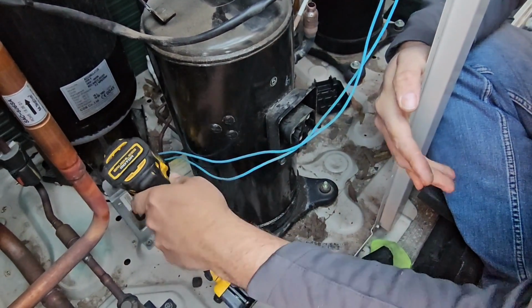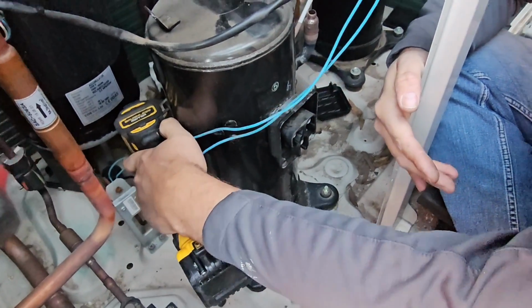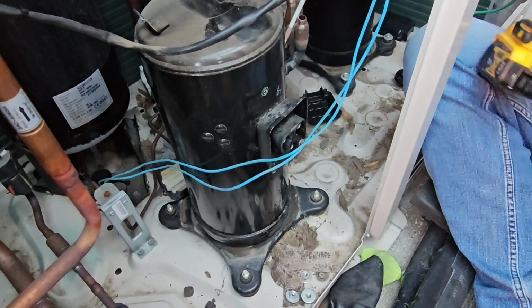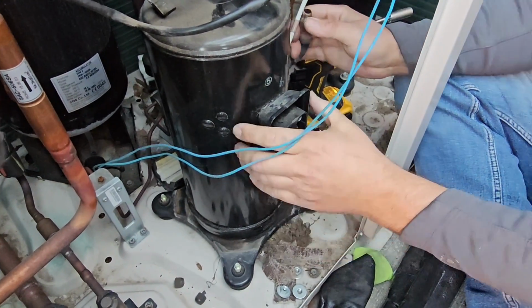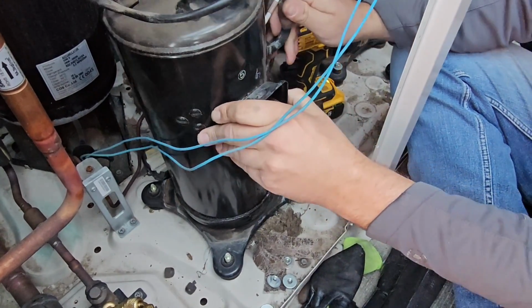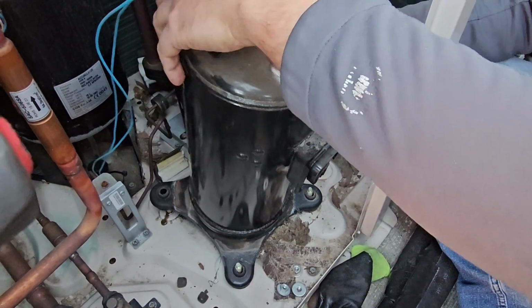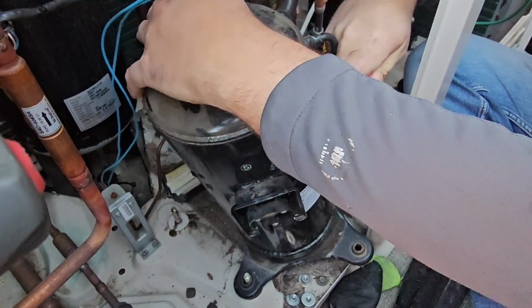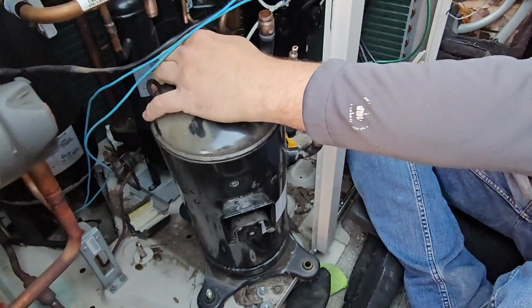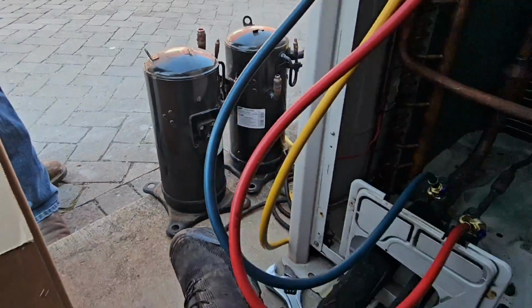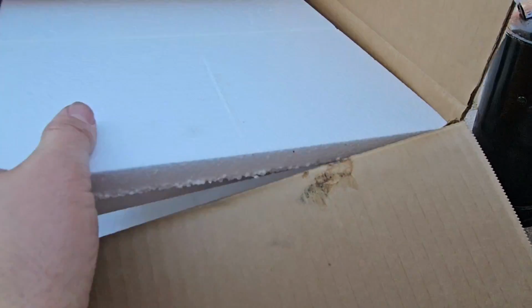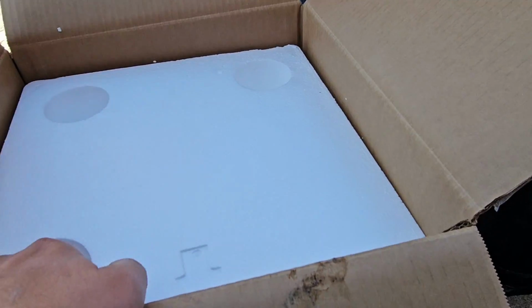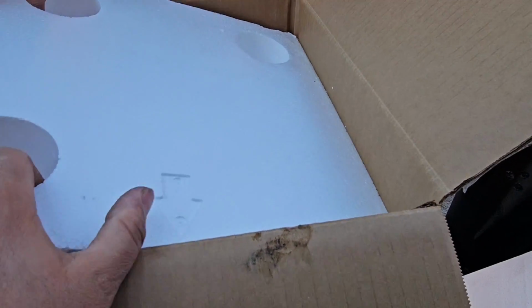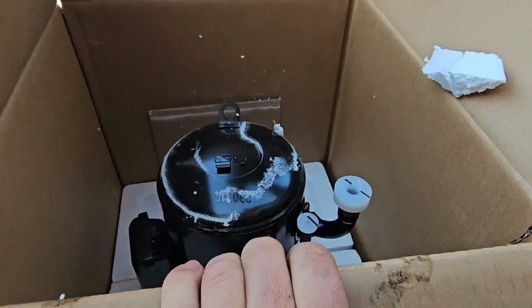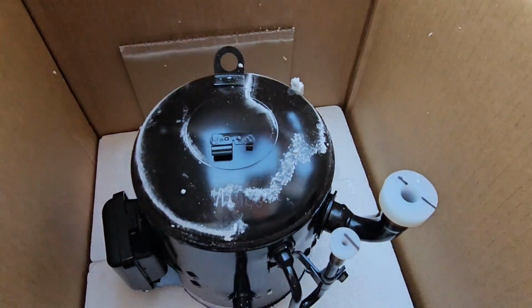Then we're going to take the new compressors, use our meter, and measure the resistance. That way you can see the difference of a good compressor and a bad compressor. So there it is. Now I'll just need to make sure I get this wire out of the way and I can take this compressor out of here. Removed both of the old compressors. Now we're going to put the new compressors in, and here's the packaging. There's the new compressor.